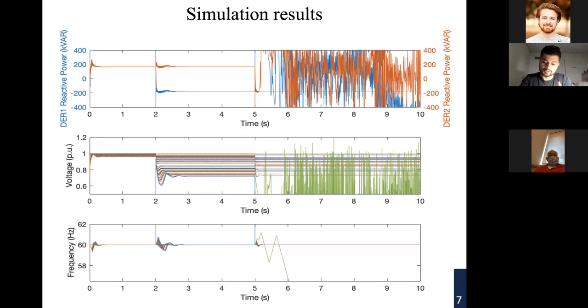One thing to note, which I forgot to mention, is that we now have these ride-through settings. Depending on your category of DER, it may ride through for some time, maybe 21 seconds. Let's say we're considering a category 3 DER. I don't want to get into the details of the standard because it just gets confusing, but it says that if your voltage level falls to between 0.5 and 0.88 PU, then it has to ride through for 21 seconds. So in that case, it is going to ride through for 21 seconds, and then it's going to trip.